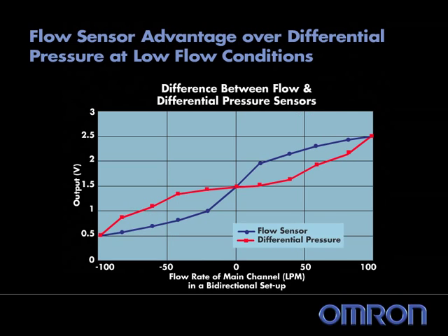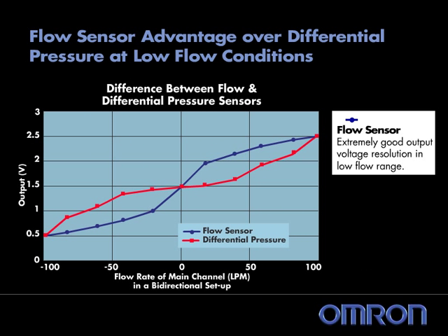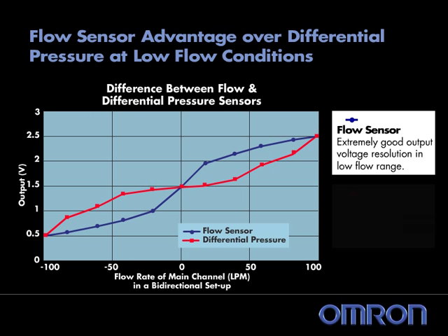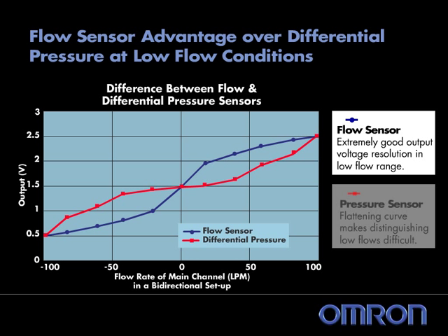This output curve is an example of a bi-directional bypass setup with a plus or minus 100 LPM flow rate through the main flow path. OMRON mass flow sensors provide excellent low-flow resolution over differential pressure sensors due to the shape of the curve as flows approach zero. Notice how the differential pressure curve flattens in the center near zero LPM.